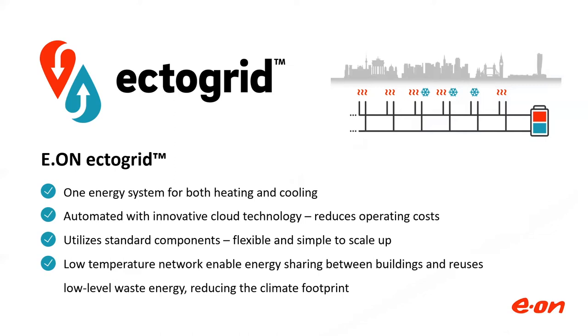It's using standard components. It's a decentralized production of heating and cooling with the help of cooling machines and heat pumps. It is a low temperature grid. When we speak about the hot pipe, it could be 20, 25, 30 degrees, which is not hot, but we help it with heat pumps. And the cold pipe could be 5, 10, 15, maybe 20. So it's a low temperature grid. We call it fifth generation of district heating, but it's Ectogrid.